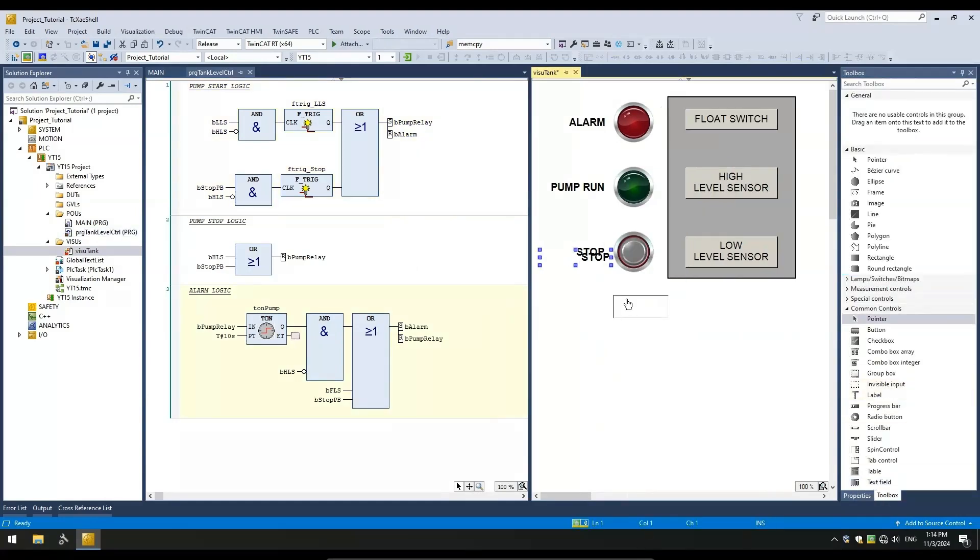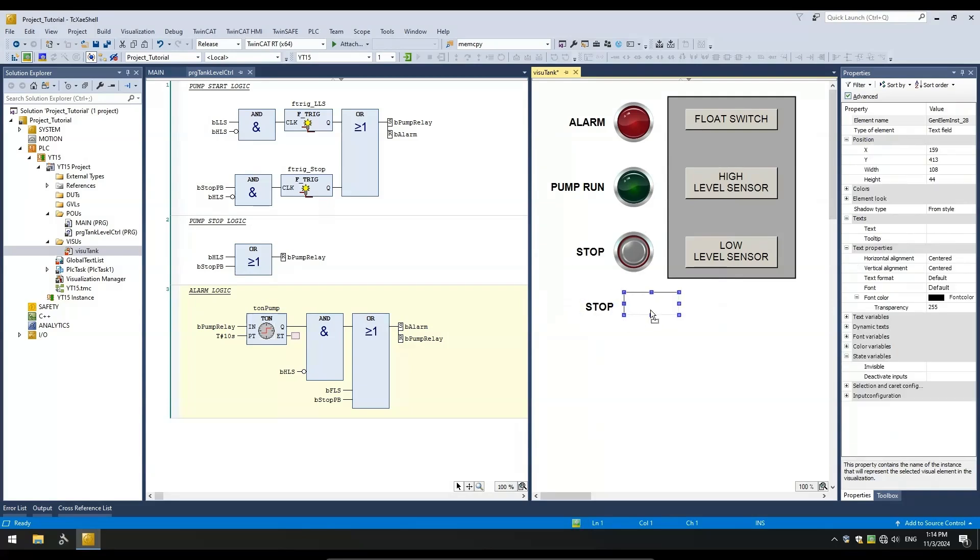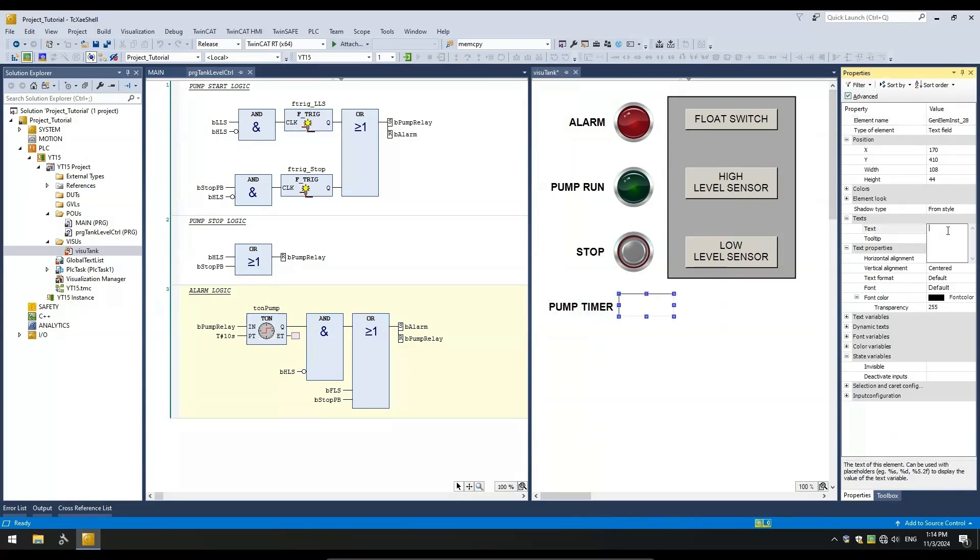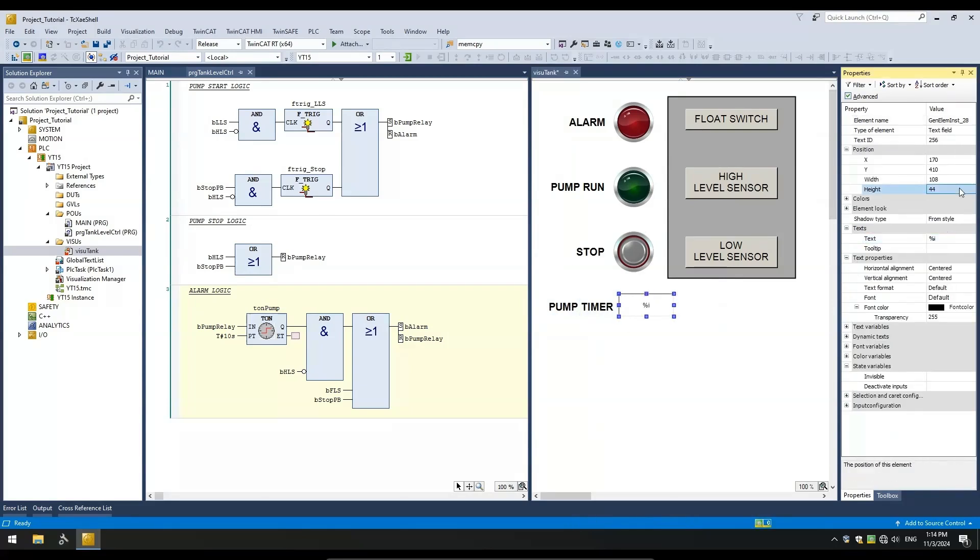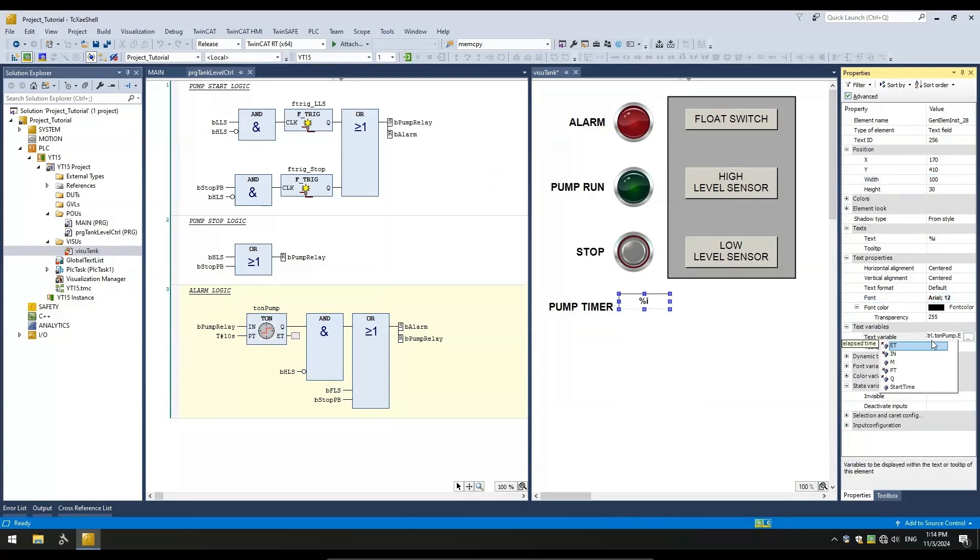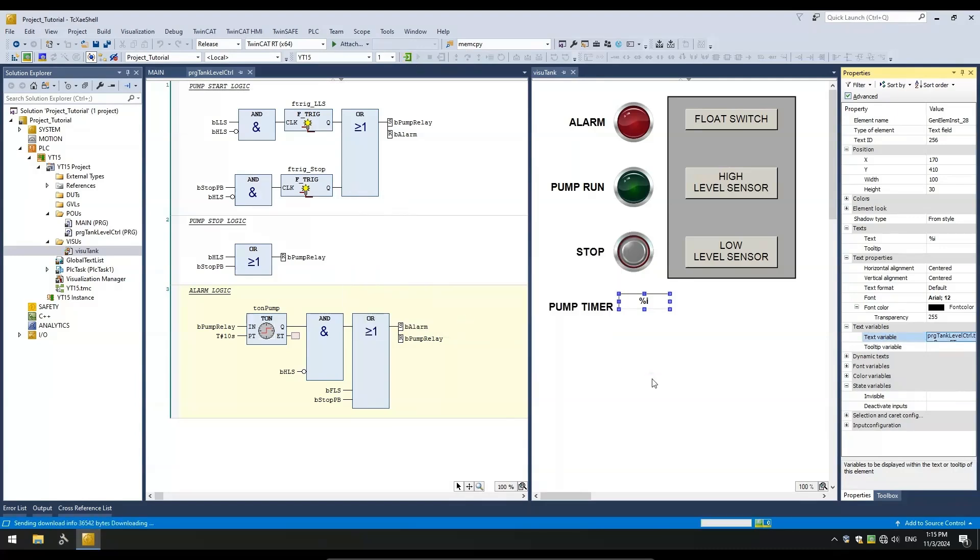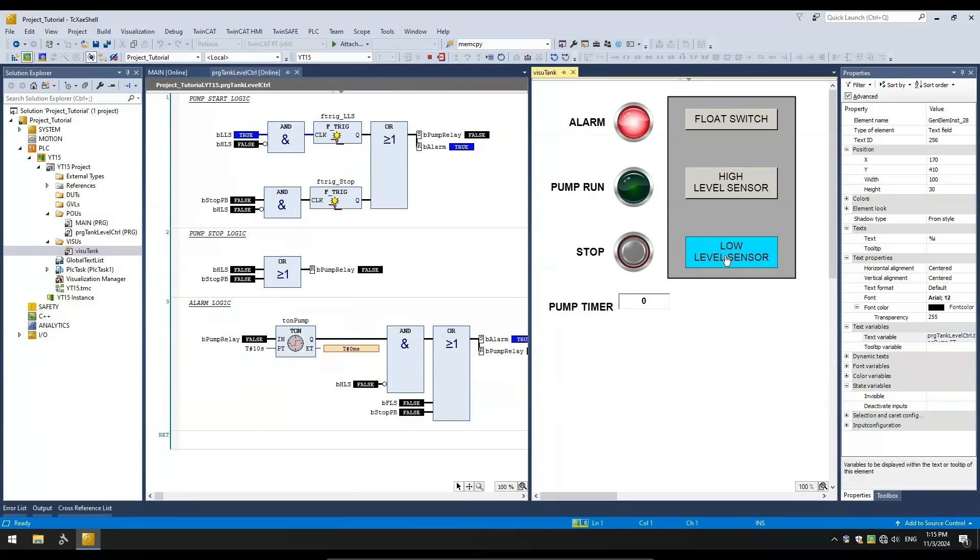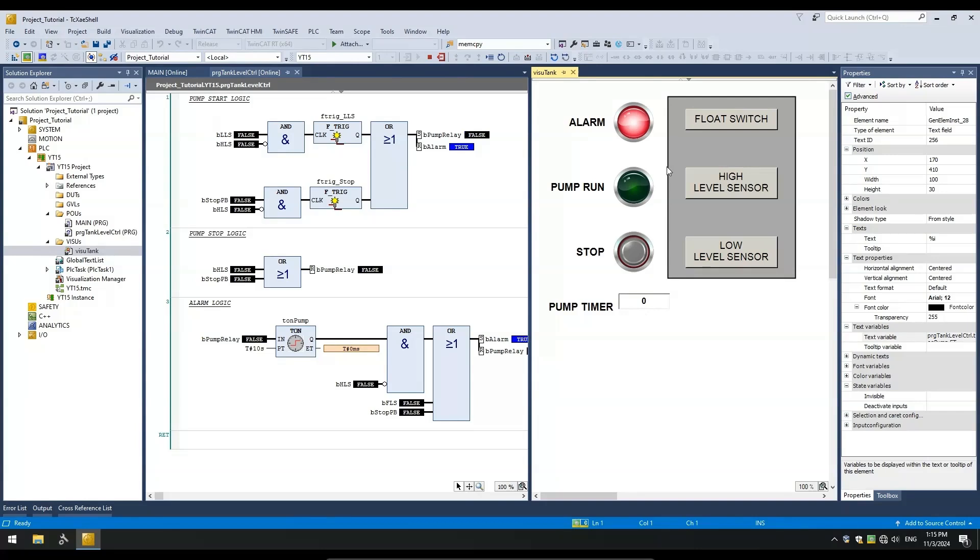For testing the timer logic, let me add the elapsed time to the visualization so we can see when the alarm should come on. Okay, let's toggle off the LLS to start the pump and we will let 10 seconds elapse before the HLS turns on. Keep in mind that the time displayed here is in milliseconds. The HLS did not turn on in time and we have an alarm. Exactly what we wanted.